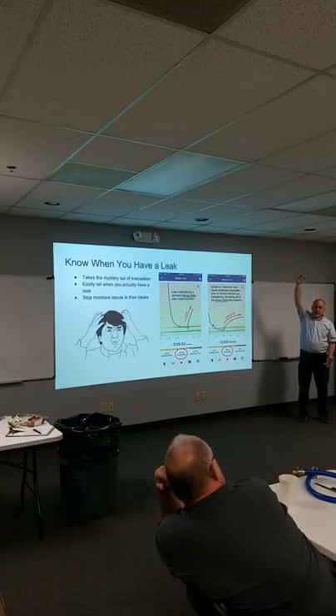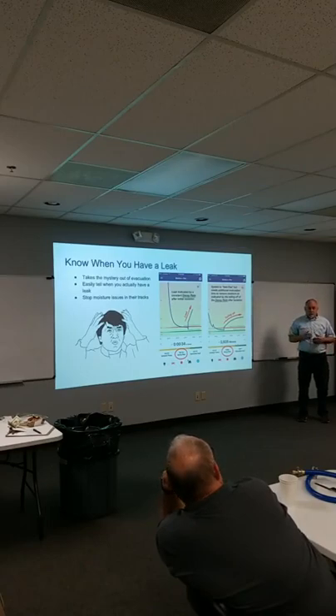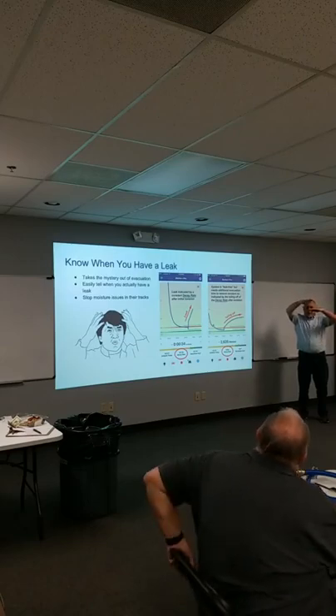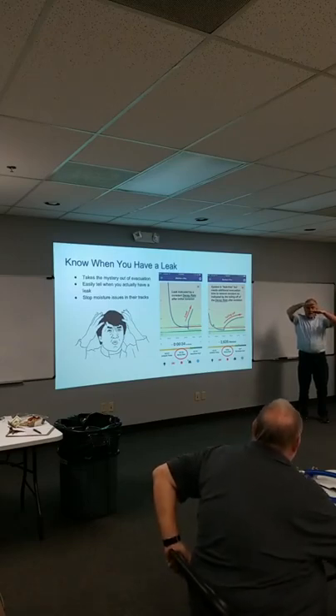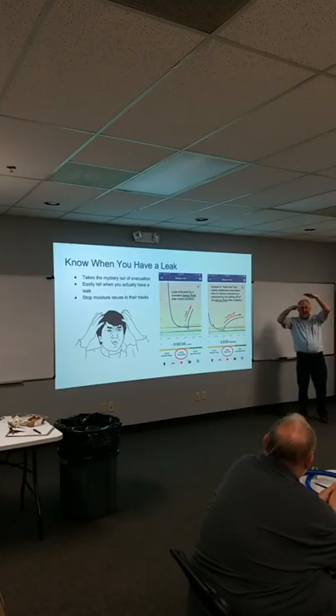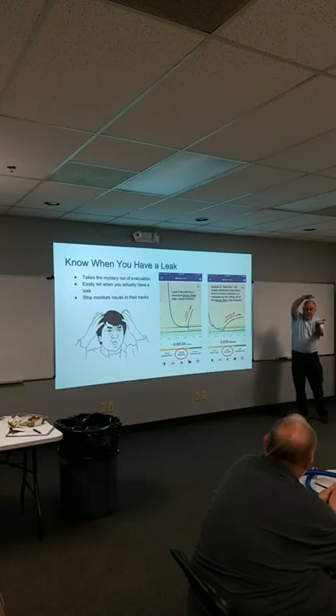So somebody said, if we're going to have this really tall iPad, we should just scrunch it down and make the graph logarithmic, which means that from 760,000 down to 20,000 microns is this big, and then it goes from 20,000 to 10, and then 10 to 5. So you end up at the bottom with this big long spot, but it's from 0 to 200, right? Which is the same as at the top of the gauge from 20,000 to 760,000. So when you squish that graph down, it's got a curve. It naturally makes a curve, right?